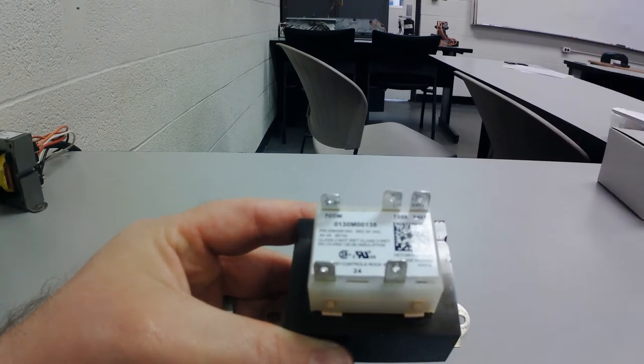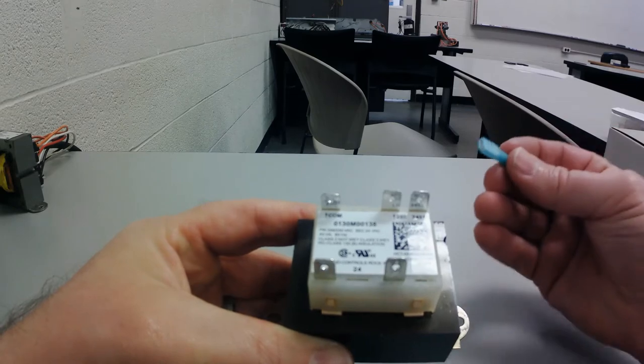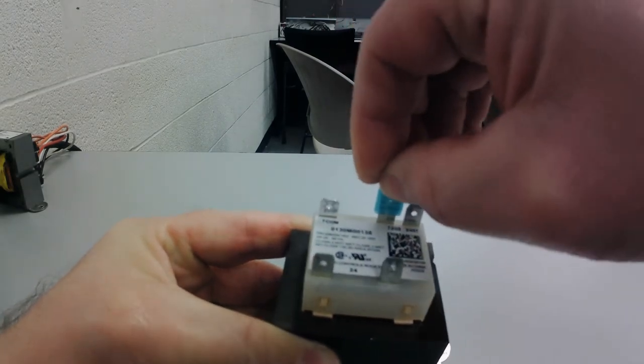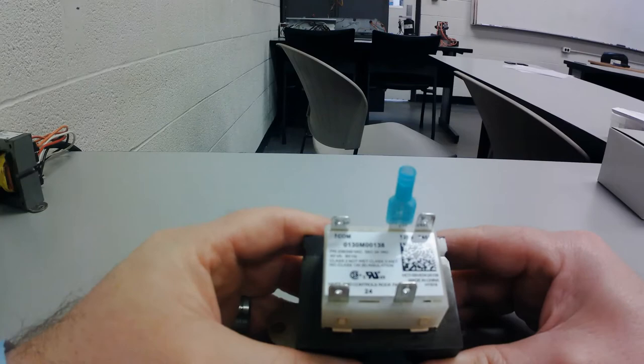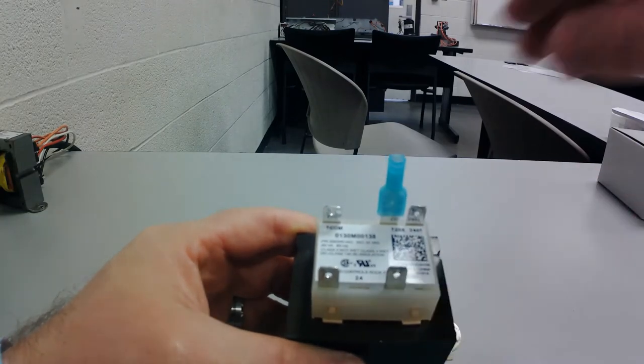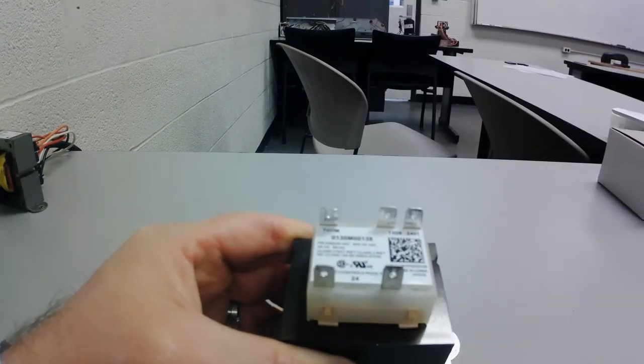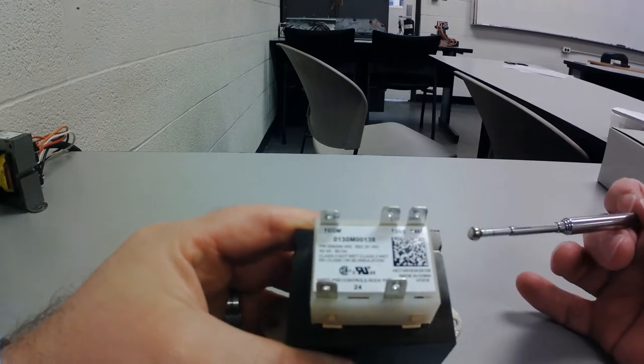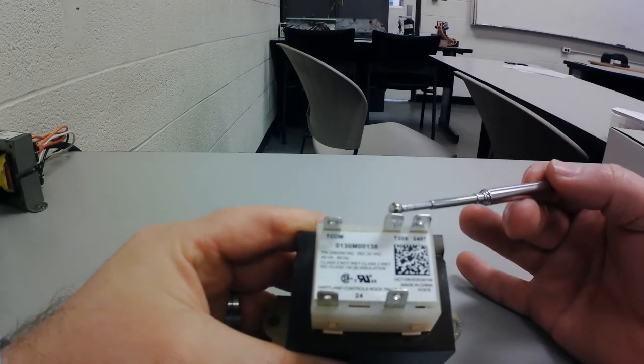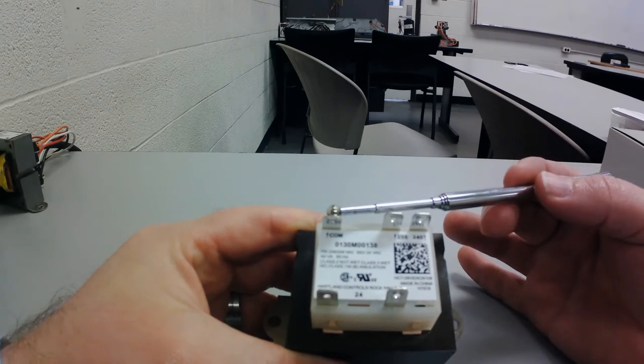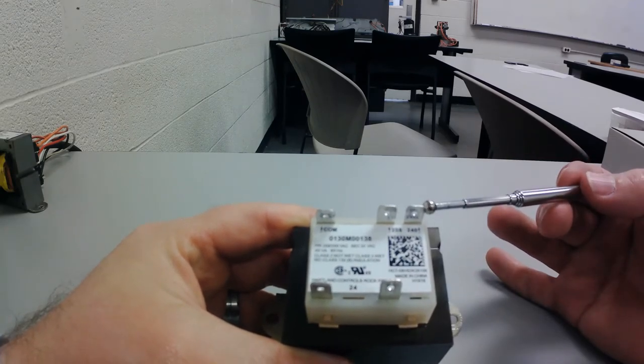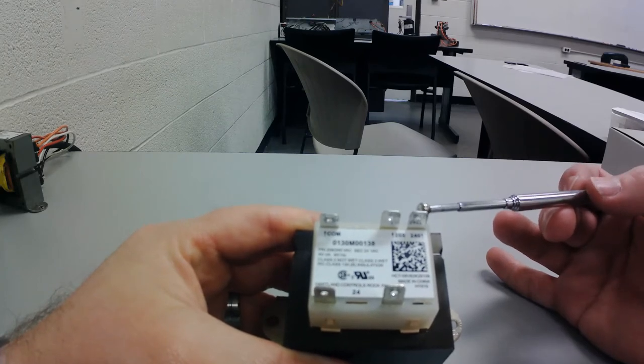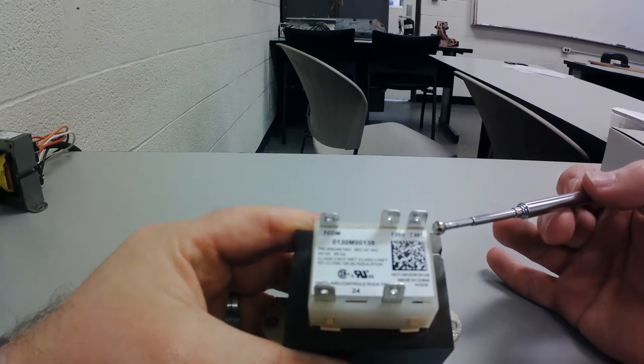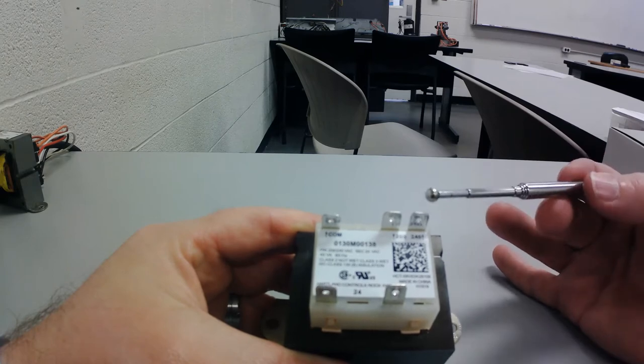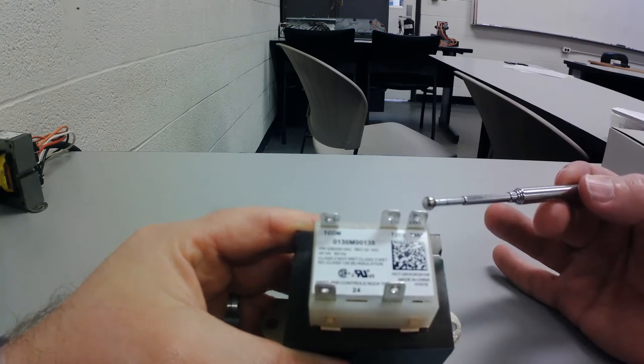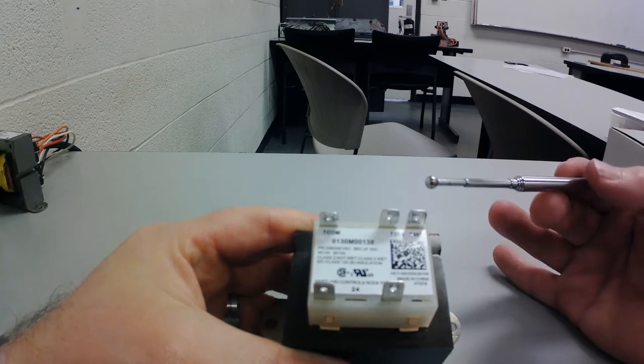In some cases, you can put an insulated terminal over it, and that way it keeps it from touching anything, such as your finger or your leads or another wire. And the same could be said if I had a 208 power source. I would use the 208 terminal and then the common to hook up my main power to it. The 240 would be left unused. But you have to watch out for these unused terminals, no matter what the voltage is, 120, 208, 240. This still carries power when voltage is applied to the unit. So you have to be careful.